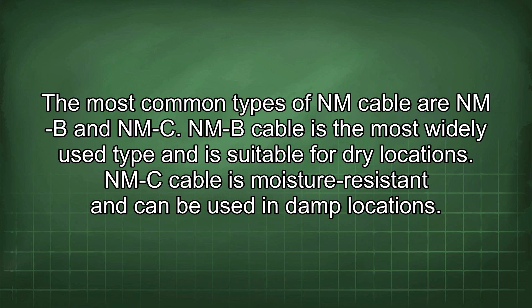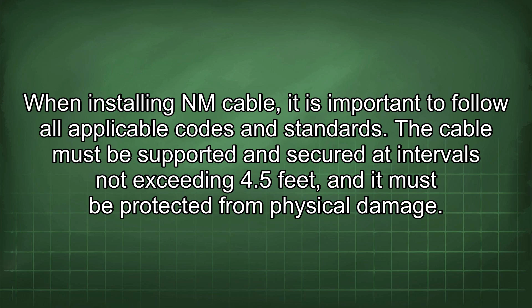When installing NM cable, it is important to follow all applicable codes and standards. The cable must be supported and secured at intervals not exceeding 4.5 feet, and it must be protected from physical damage. NM cable must not be installed in wet locations or where it is exposed to direct sunlight unless it is specifically listed for those applications.